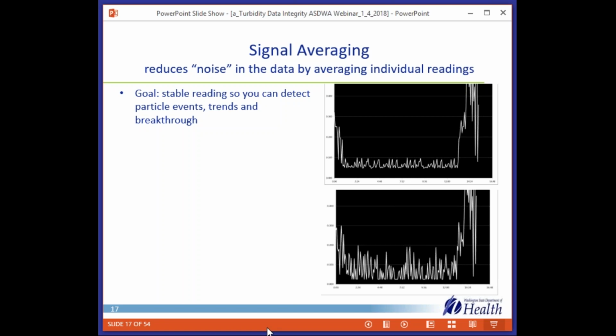The next thing we looked at was signal averaging. So this is a setting that reduces noise in the data by averaging individual readings. And the goal here is getting a stable enough reading so that you can detect particle events, trends, and breakthrough in your data. So the typical options for this are 6, 30, 60, and 90 seconds.